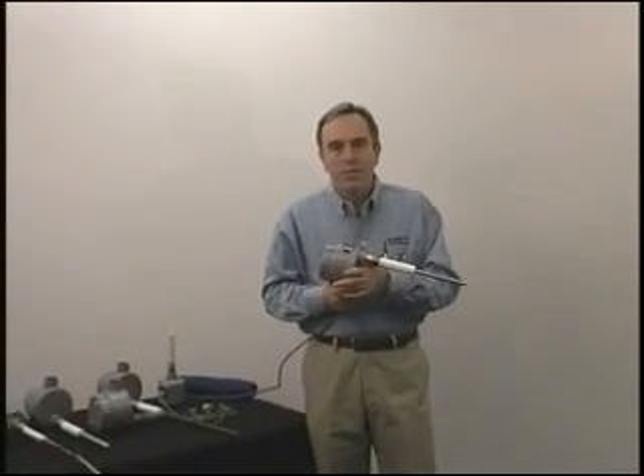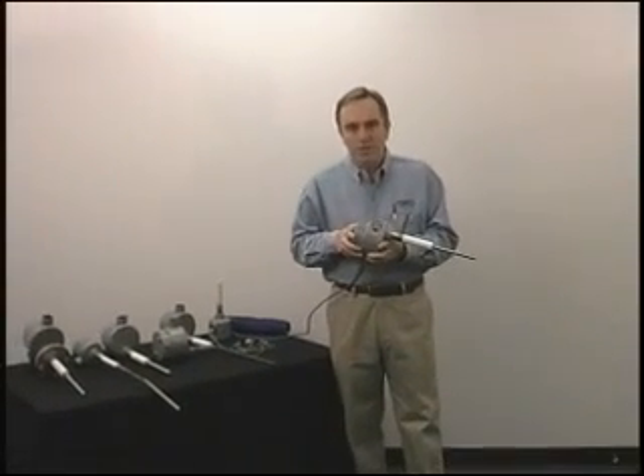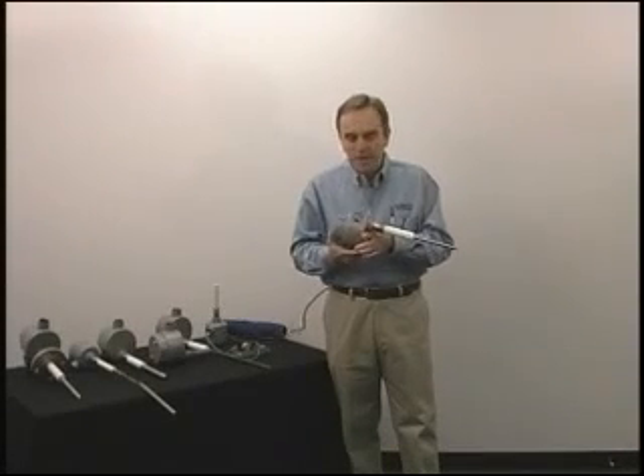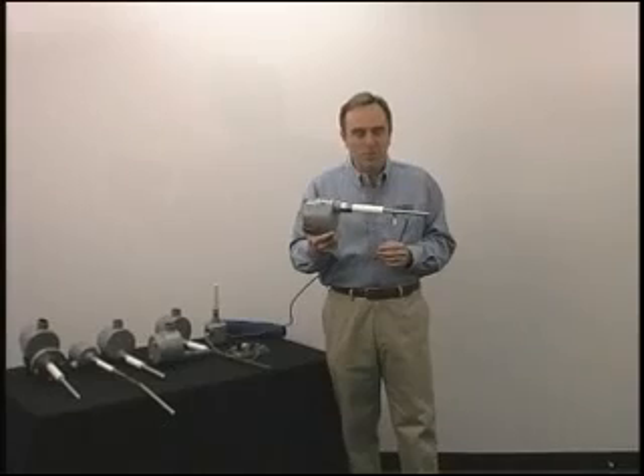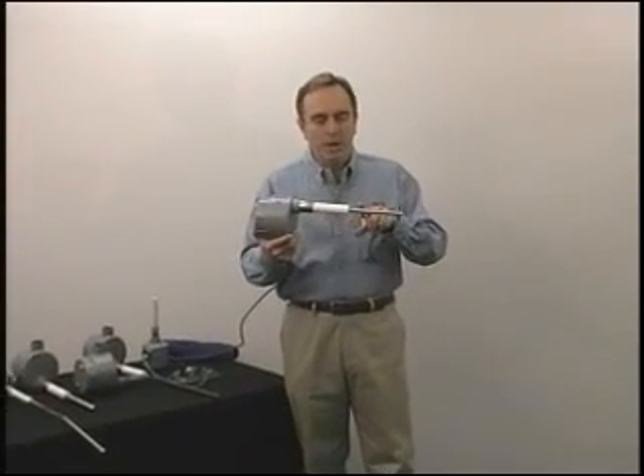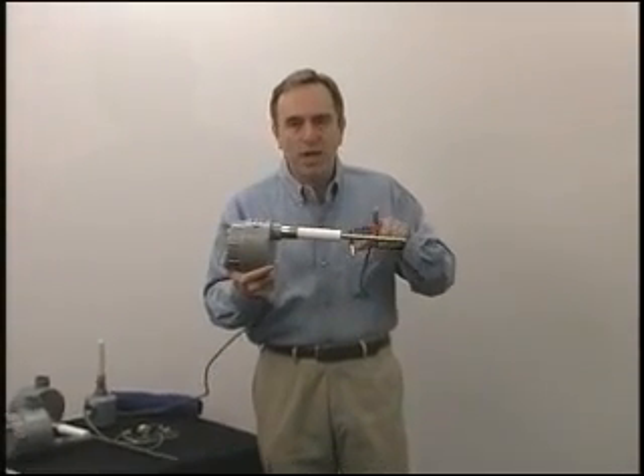Today I'm going to show you a radio frequency level switch, which is a handy switch to have in your bag of tricks because it will measure both liquids and dry materials. This is the LS7000 level switch, and the way it works is we put a 1.3 megahertz sine wave on the probe and adjust the amplitude of it. Then anything that comes into contact with the probe decreases the amplitude of the signal, and that's what we sense.